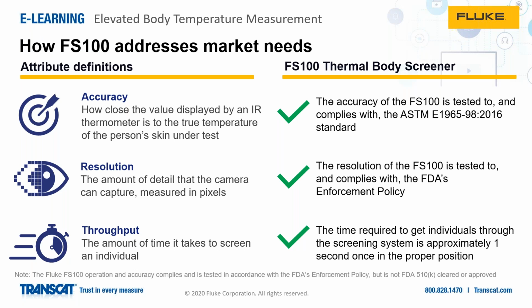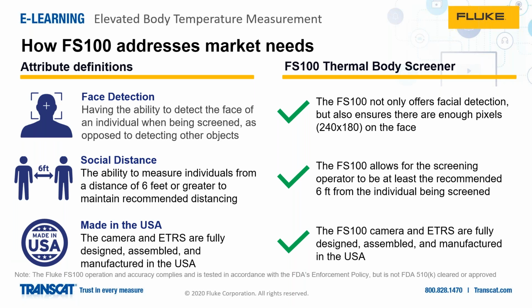So the FS100 addresses some similar attributes as the 67 Max, but slightly different given that we're looking at a 2D thermal image view. So we'll go into this a little bit. Again, the accuracy is tested to what's outlined in the FDA's enforcement policy. The resolution of the FS100 is tested to and complies with the FDA's enforcement policy, as we've just talked about, and some of the IEC standards that are called out in there. From a throughput standpoint, the product allows for about a 1 second per person throughput, so it's quite quick, and you get some social distance, which we'll talk a little bit about here.